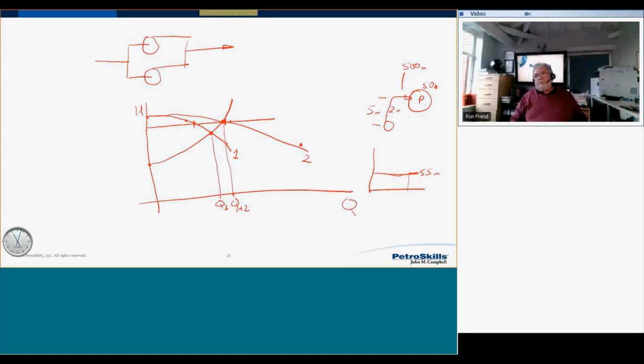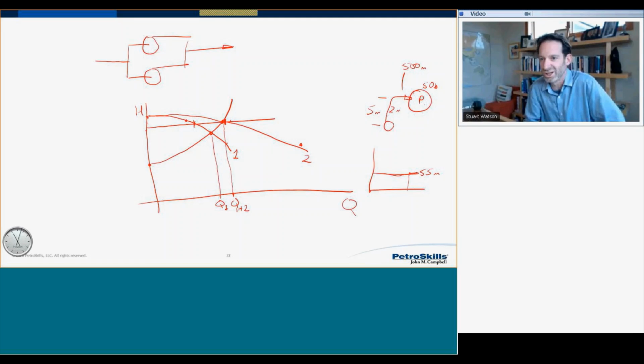And the only comment that I'd have to the question, I'm just trying to look for the question in the Q&A blocks, is that this dialogue that you can see Ron's going through here is based around two identical pumps. And when you're adding a new pump to the system, and we're talking centrifugal pumps here as well, you've got to look at adding the two independent pump curves. And so what you'll notice in the discussion that Ron's had here is that by running two pumps, you have affected the performance of the existing pump as well as the performance of the new pump.